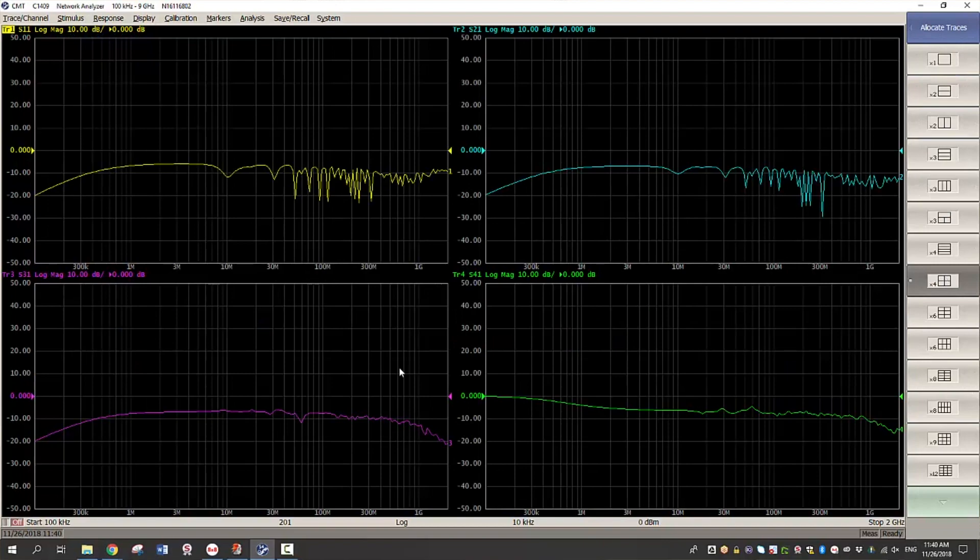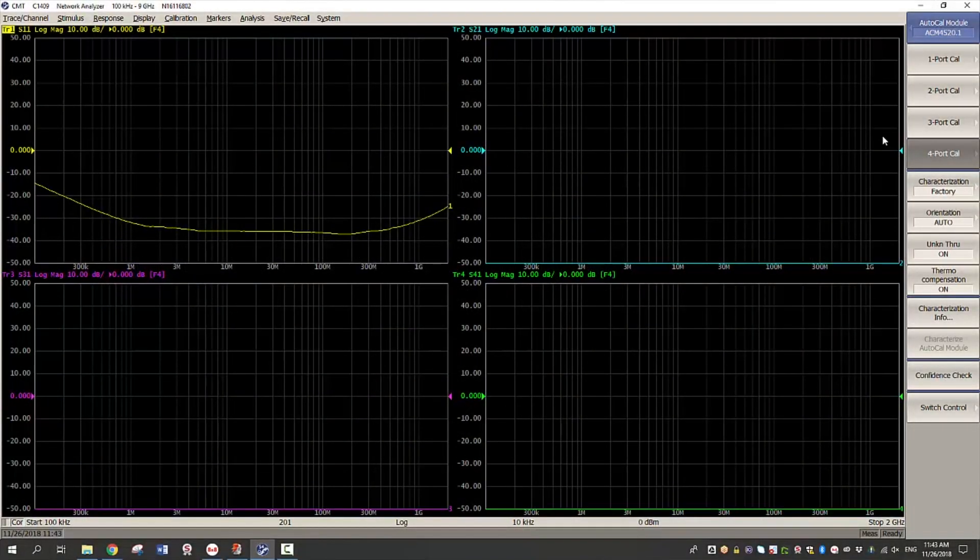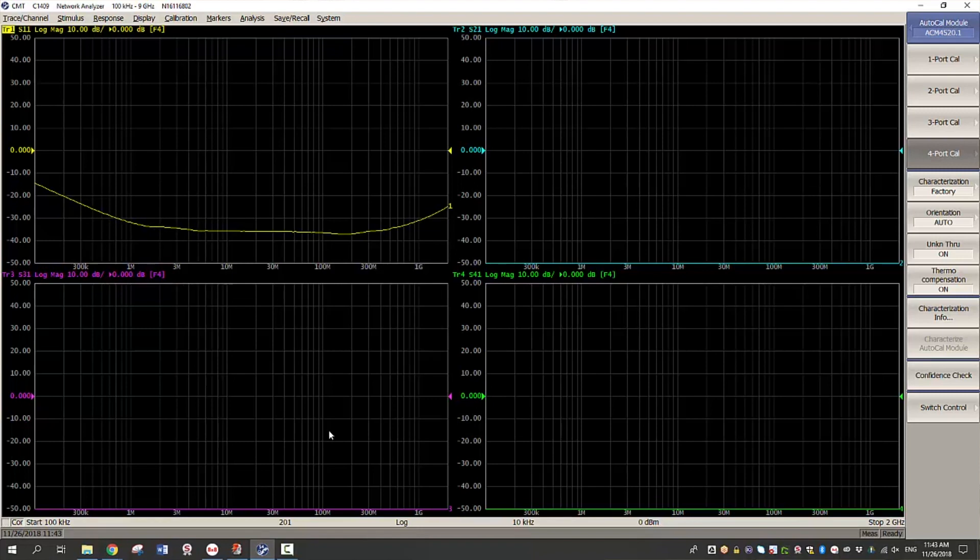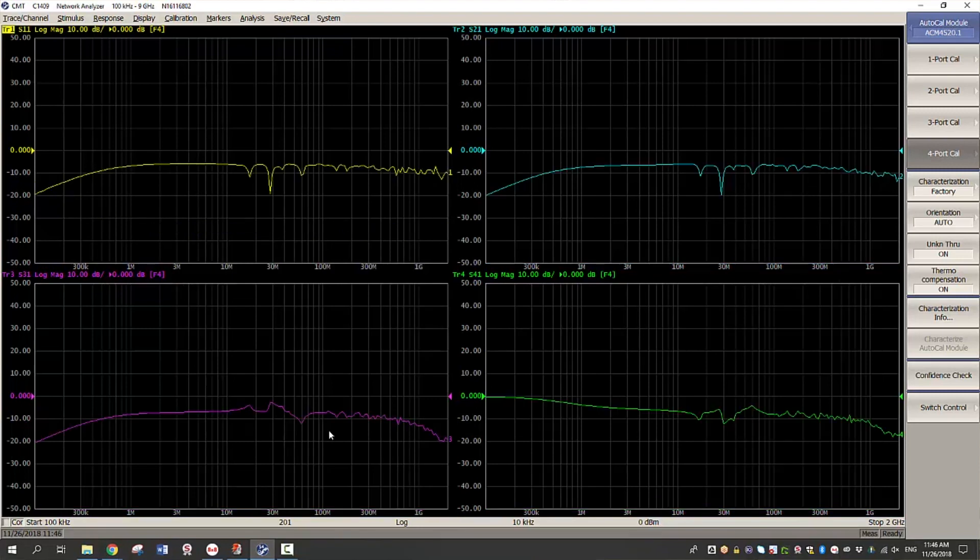At this point we have finished calibration. Your F4 on the trace status field and COR on the lower bottom left corner of your screen indicates that the calibration has been applied. At this point the calibration plane is at the end of the coaxial cable.